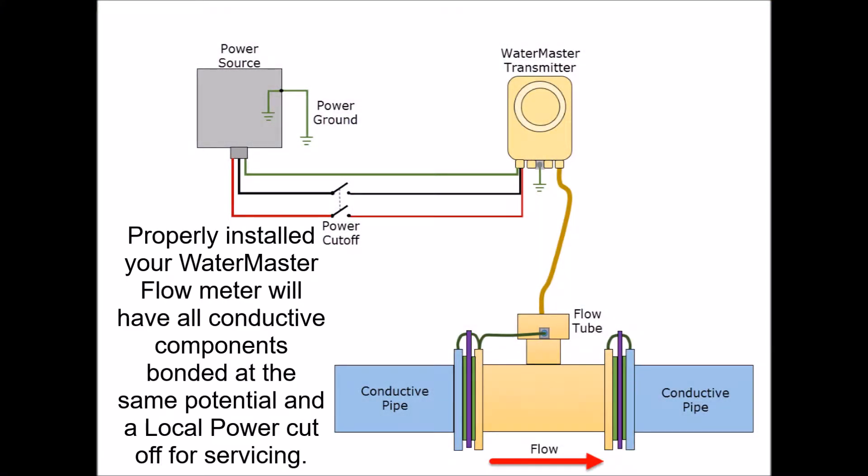Properly installed, your WaterMaster Flow Meter will have a local power cut off for servicing, bonding of the transmitter housing to earth, power source bonded to earth, sensor head bonded to one flange, both flanges bonded to their respective ground rings or plates, and if the pipes are conductive, flanges bonded to flanges. It should be noted that you must not ground cathodic protected systems. Also, all WaterMasters require at least one ground ring upstream.